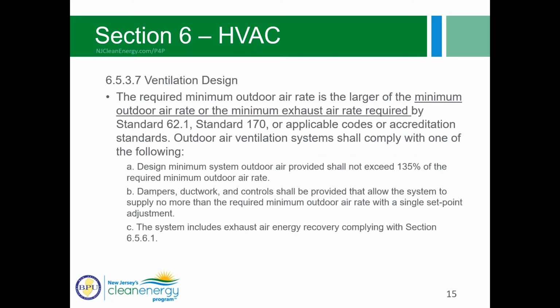All right, so with ventilation design, we do see a good number of projects that have ventilation that exceed requirements, and there's always been a penalty for this. So this would also impact the prescriptive requirements. So we also need to include that in the modeling, and it would show up as a penalty. So looking at these different standards, it's good to pay close attention to what the ventilation requirements are, and that we're modeling and sizing equipment appropriately around that.